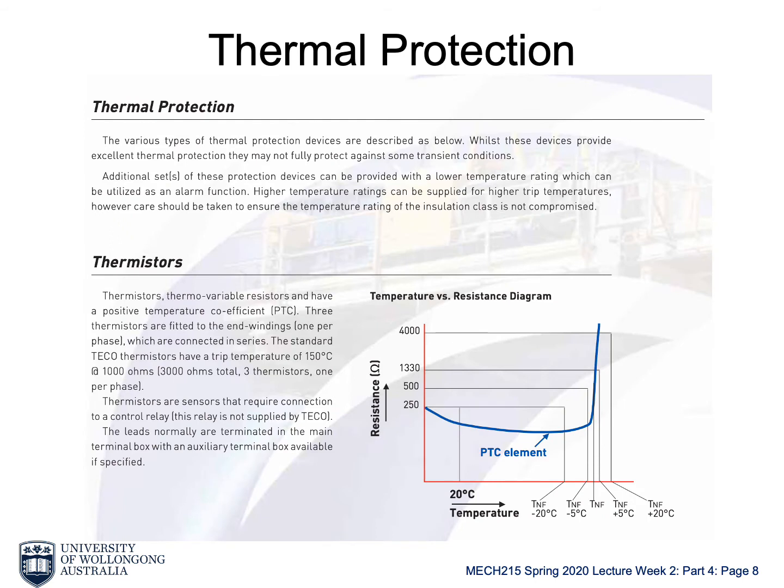The motor actually has its own protection mechanism by connecting a PTC element, which is kind of a resistor, but normally its resistance is very small. But when the temperature increases, its resistance can go extremely high. You can look at this blue curve. After the temperature gets to TNF, the resistance goes 100 times higher than normal. So in that case, it can limit the current going through, kind of forcing the motor into a protection condition to stop the motor from getting too much heat and getting too hot.